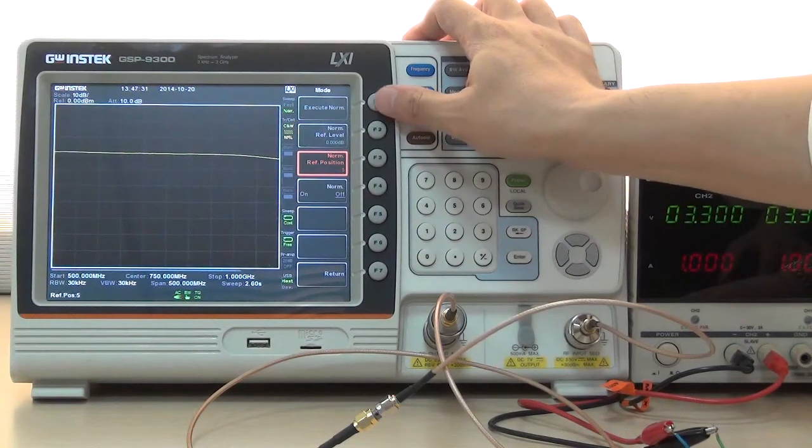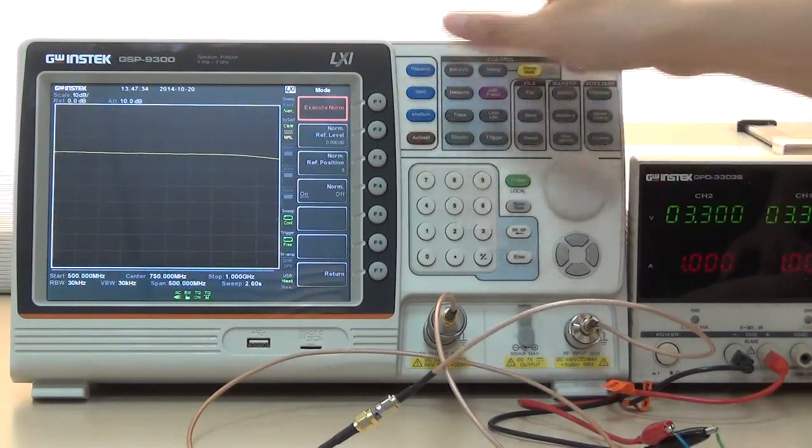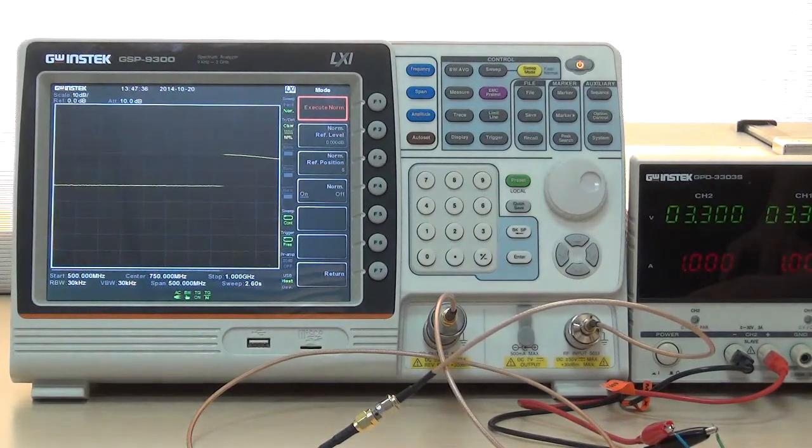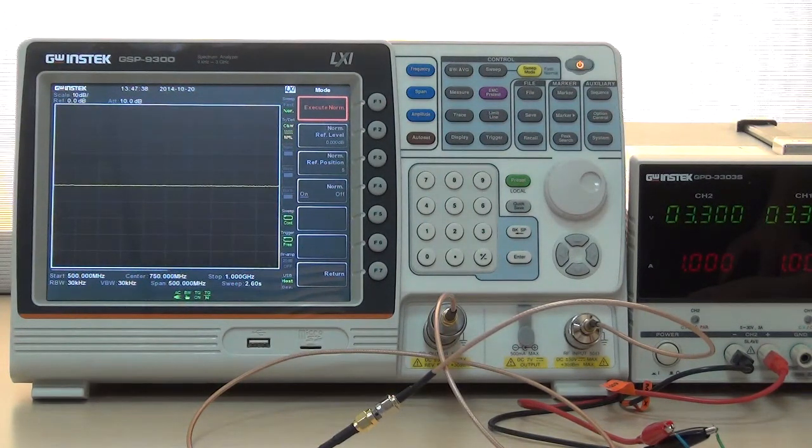Next, press F1 to execute Normalization. After completing Normalization, disconnect SMA RF cable and adapter. Next, connect Low Noise Amplifier Component to conduct Scalar Network Analysis Test.